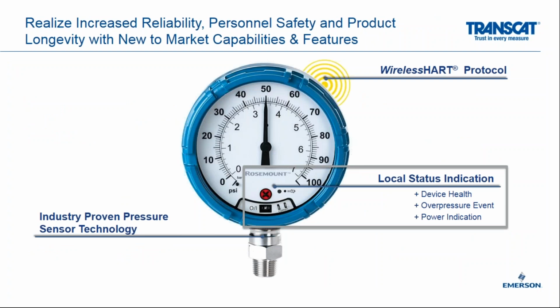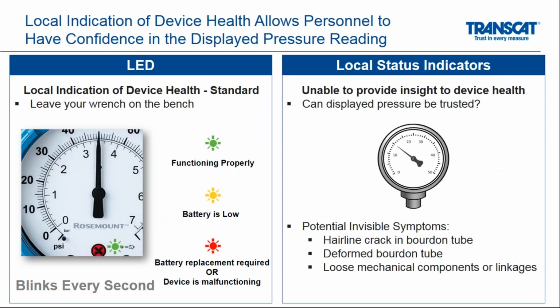So I'm going to talk a little bit about the actual local status indication. This is not, again, some sort of big LCD screen that's going to tell you in words what's happening, but it still can be a very valuable piece of gauge technology to give you some more insight, to understand the health of that gauge. So the first part is just an LED light. It's green, it's yellow, and it's red. And if it's green, that means it's functioning properly. Yellow generally is going to mean the battery is low.